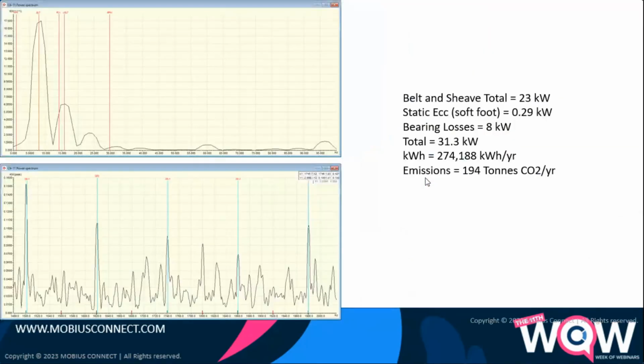That comes out to, pardon me, sorry about that, 23 kilowatts from the belt and sheave, from a slight overtension. The static eccentricity or the unbalanced magnetic pull, which means that it's trying to pull towards the side, 0.29 kilowatts. But that unbalanced magnetic pull is also hitting the friction in the bearings, increasing those losses to 8 kilowatts. So I've got a total loss in this case on a machine of 31.3 kilowatts. That's excluding anything else. And that comes out to, using that same 8,000 hours, 274,000 kilowatt hours a year, or 194 tons of CO2.